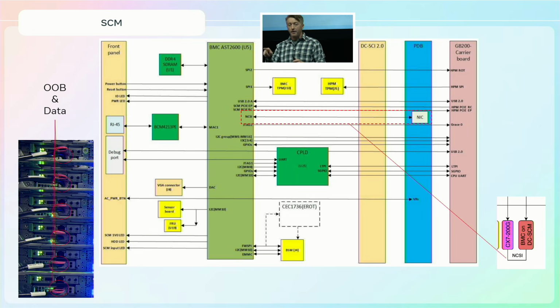Another one of those LEDs very quickly represents the output of that 12 volt. If that LED is on, you can confidently say the 12 volt conversion on the PDB is taking place. That is really good. The PDB is buried in the bottom of the tray, and if you have to service it, it's a very high effort, high cost, high risk one, because you have to completely disassemble the tray, put it all back together, and something else may go wrong. So you want very high confidence that if you say the PDB is broken, you have a quick way to actually verify that, and not just be part swapping to try to fix it.